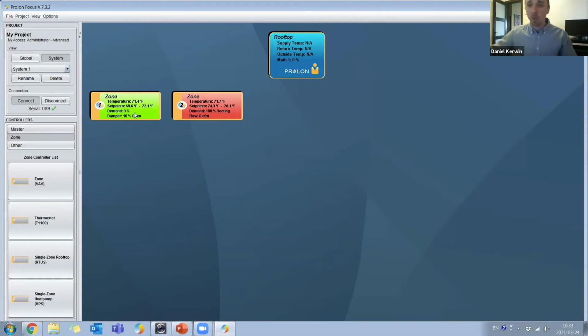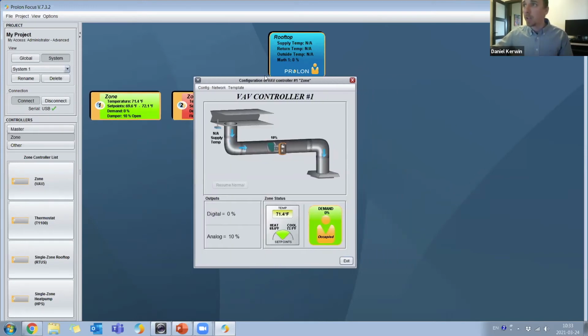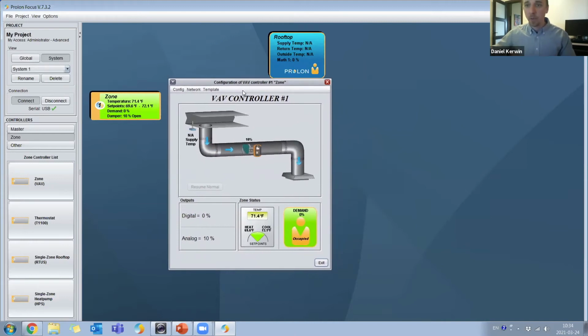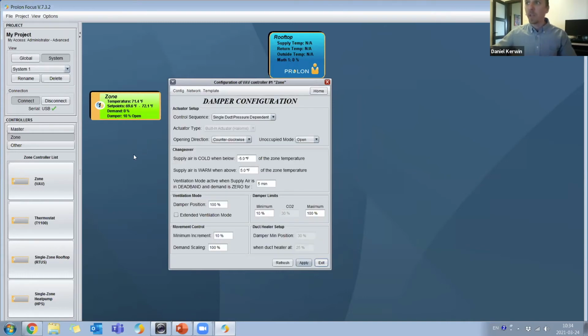So if I were to, let's say I want to configure one of these devices, I just double click on it. And there we go. So here's the default view for a VAV controller. So we can see the actuator, temperature in the supply, our space temperature with our set points. And here we have our outputs. So let's say I want to configure one of these aspects. I could do config damper. It brings me to the damper configuration page.